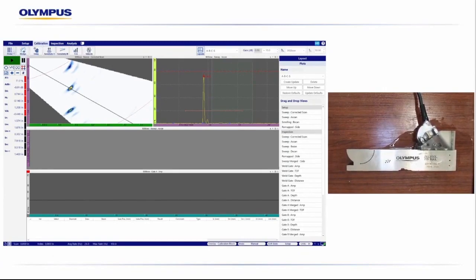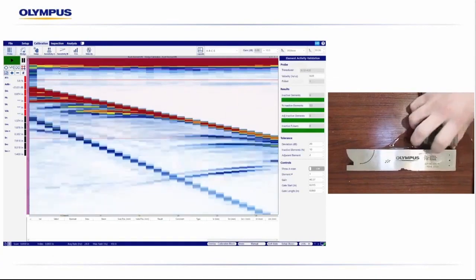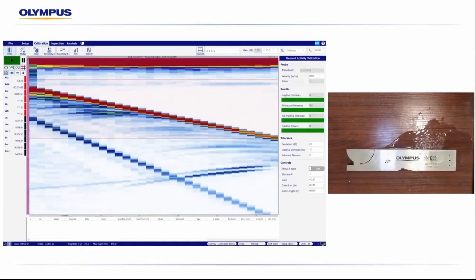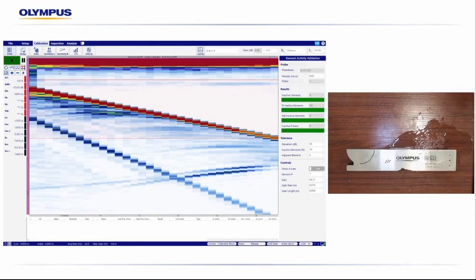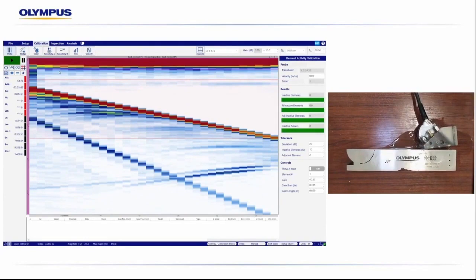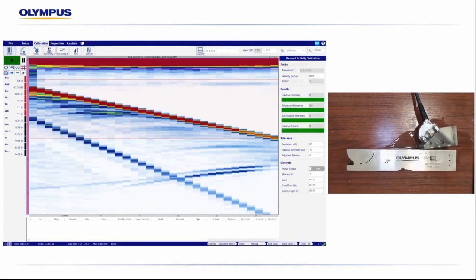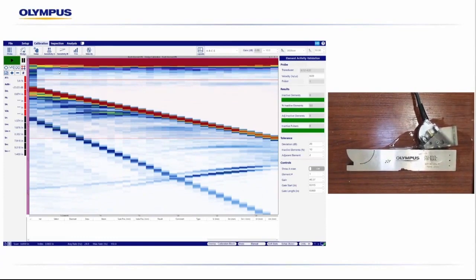Moving to the calibration tab on the top side of the screen, we'll click our probe check. We've got our probe, wedge check, wedge delay, sensitivity, and TCG, and your velocity. Within our calibration and our probe check, we can verify we don't have any active false triggers, inactive elements, anything like that. Same within our wedge check. That'll check our wedge to the default parameter from BeamTool, and that'll verify our wedge height, angle, and that everything is correct within the set specifications that we provide.